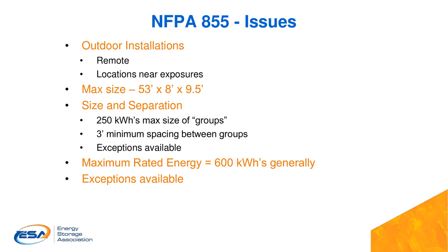So size and separation, this is getting into kind of the meat of the standard. This is 250 kilowatt hours maximum size of groups under NFPA. As you'll see here in a few minutes, the IFC is different. The IFC is 50 kilowatt hours. So that's a pretty substantial difference in the two. 3 feet minimum spacing between groups, and that's the same for both. There are exceptions available. 600 kilowatt hours maximum rated energy for areas. And so if you wanted to put in more than 600 kilowatt hour storage inside of a building, you couldn't do it. That doesn't mean you can't put more than that in a building, but you'd have to divide it into several spaces. Again, there are exceptions.